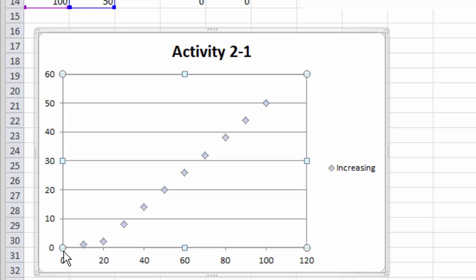And you send the signal to the controller. And there's some slop in the mechanical portion of the valve assembly. And as you're trying to increase the valve position, it just doesn't respond for a little while until all that slack's taken out. So there's one. So we've got the increasing data on here.